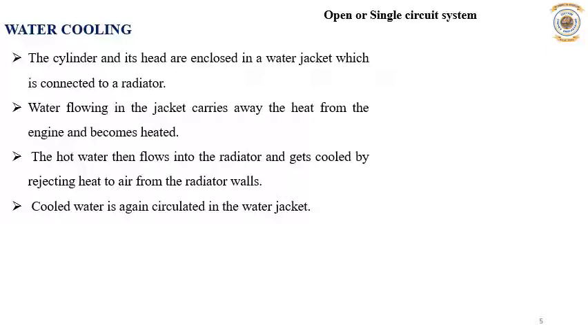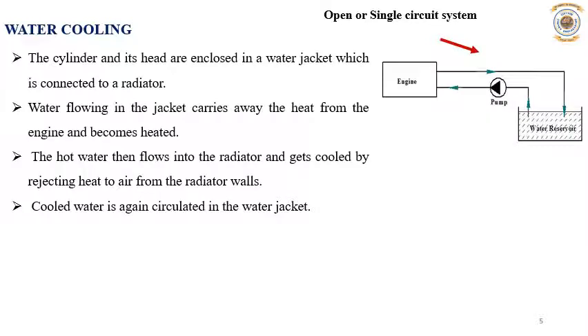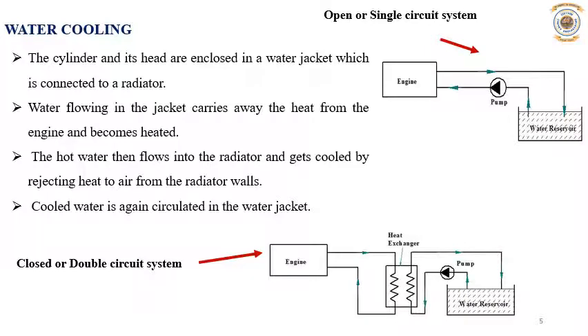There are two types of water cooling systems. The first is the open or single circuit system: water from a reservoir is pumped to the engine and then directly fed back into the water reservoir. The second is the closed or double circuit system: a pump circulates water from a reservoir to a heat exchanger, where it exchanges heat with water coming from the engine. The hot water from the diesel engine gives heat to the secondary circuit water, gets cooled, and then goes back to the engine.